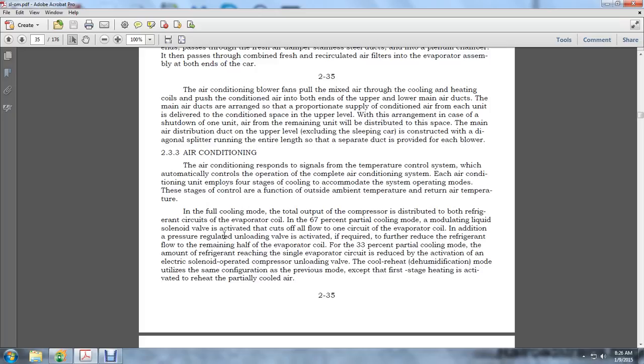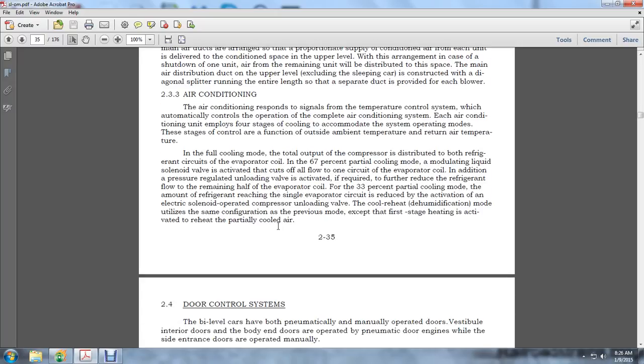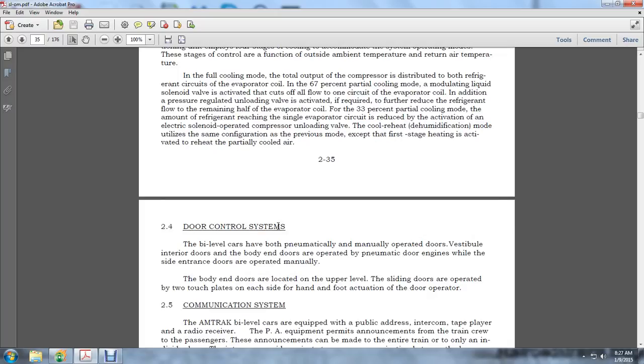In the 67% partial cooling mode, a modulating liquid solenoid valve is actuated that cuts off all of the flow to one circuit of the evaporator coil. In addition, the pressure regulated unloader valve is activated, required to further reduce the refrigerant flow to the remaining half of the evaporator coil. For the 33% partial cooling mode, the amount of refrigerant reaching the single evaporator circuit is reduced by the electronic solenoid operated compressor unloading valve, and the cooling reheat dehumidification mode utilizes the same configuration as the partial cooling mode, except for the first stage heating activated by the reheating of the partially cooled air.